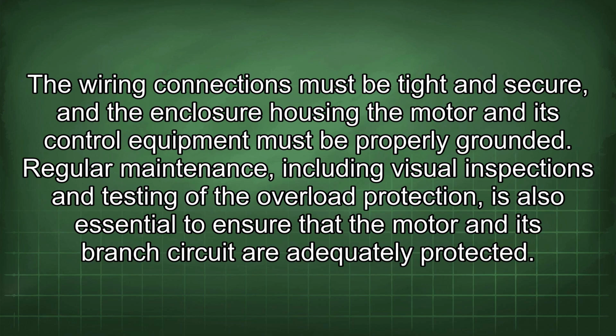The wiring connections must be tight and secure, and the enclosure housing the motor and its control equipment must be properly grounded. Regular maintenance, including visual inspections and testing of the overload protection, is also essential to ensure that the motor and its branch circuit are adequately protected.